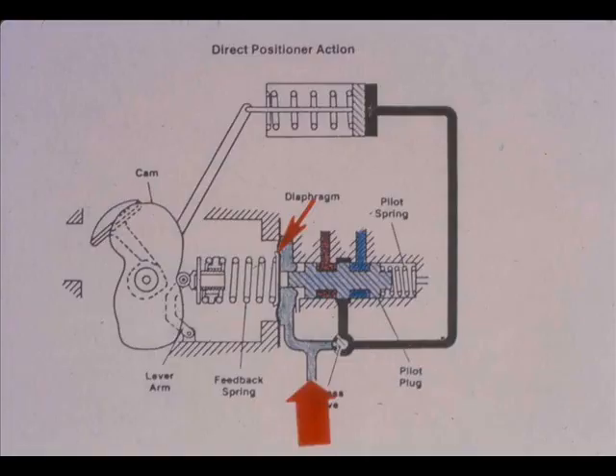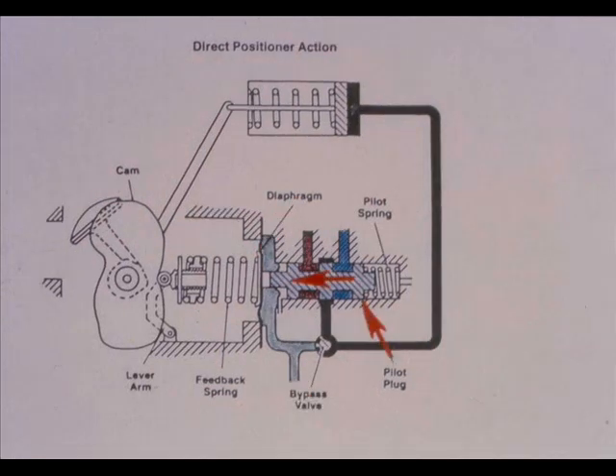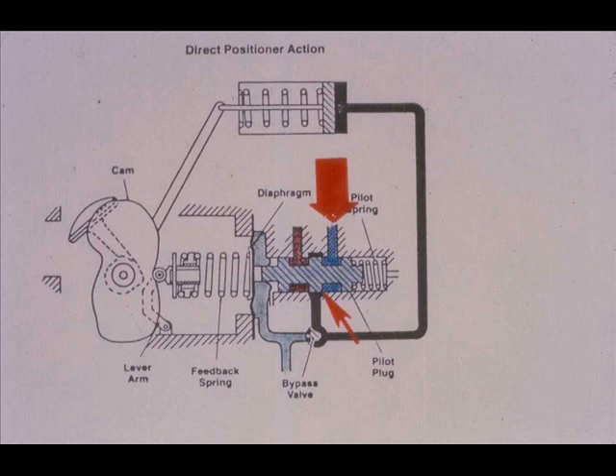For the direct acting positioner, as the input pressure increases, the diaphragm assembly moves to the left. The pilot plug follows the diaphragm assembly movement because the pilot plug is pushed by the pilot spring. As the pilot plug moves to the left, it connects the output circuit to the supply circuit, thus increasing the pressure on the actuator.